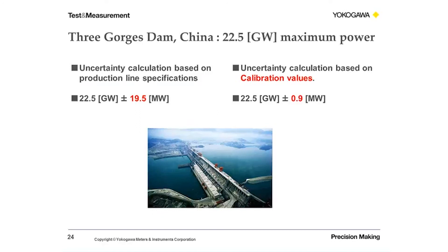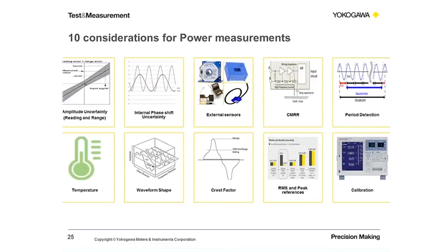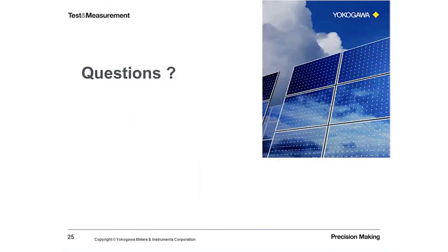It's nice that you tied this back to where we started, Michael. We've covered 10 key considerations for power measurements: uncertainty in voltage, current, and power amplitudes; effects of internal phase shift uncertainty; effects of sensors and probes; CMRR; importance of period detection; validity conditions for uncertainty specifications such as temperature, waveform shape, and crest factor; the impact of RMS versus peak range specifications; and finally how calibration helps us verify instrument reliability. Thank you for joining us today — we'd love to take any questions now.